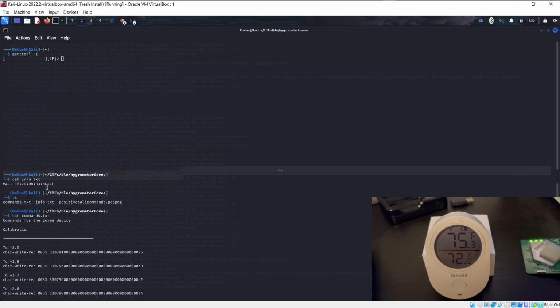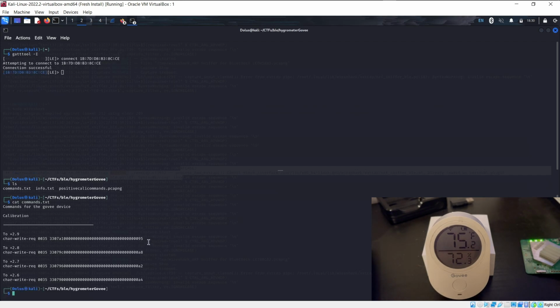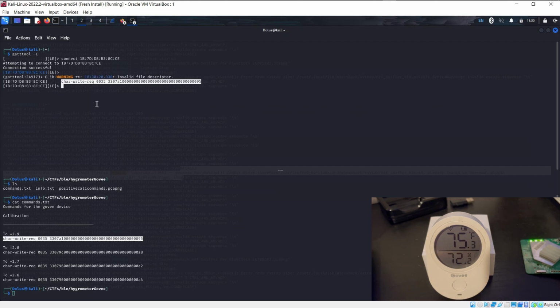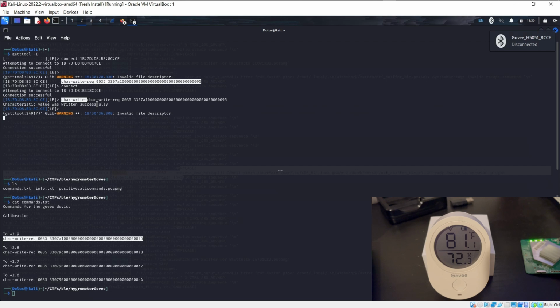We're going to connect using gatttool, as you've seen previously. Now that we're connected, we'll take this max value for the calibration limit and send it. Oh, it disconnected, so we'll connect again, and once connected we'll send this command and see it actually changed the value. It only went up 6 degrees, but depending on the application, 6 degrees could be a lot or maybe not enough.